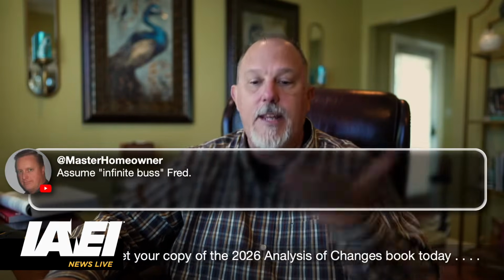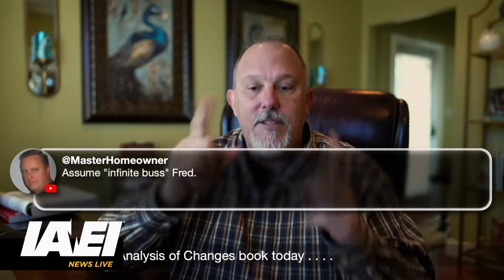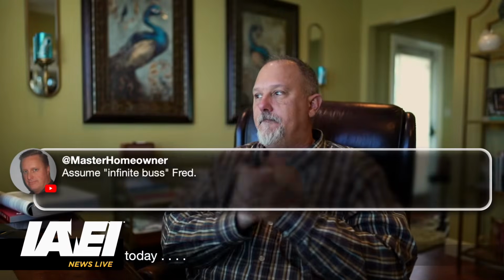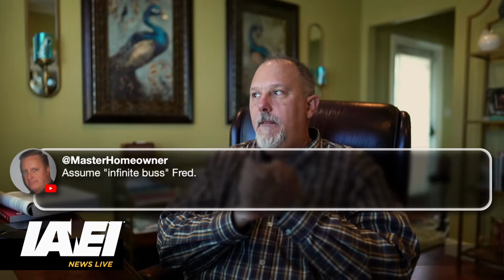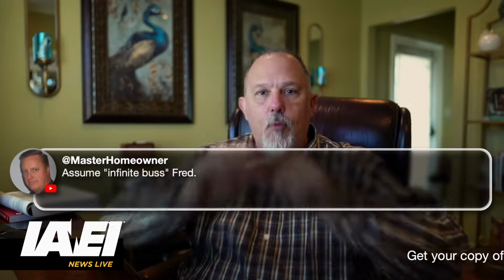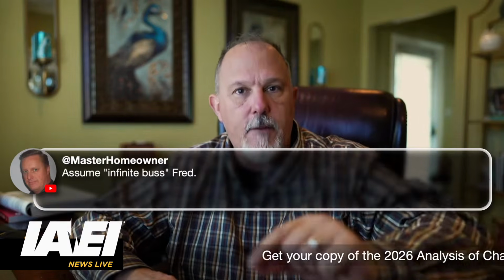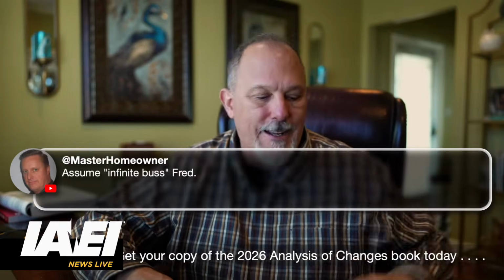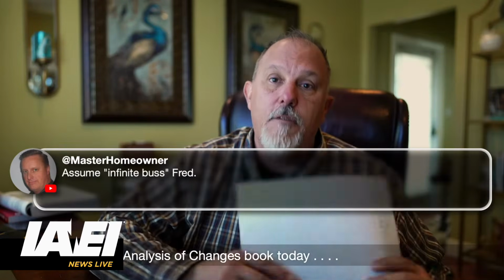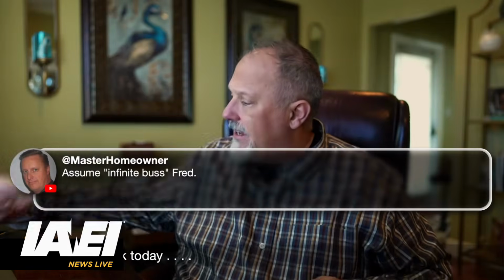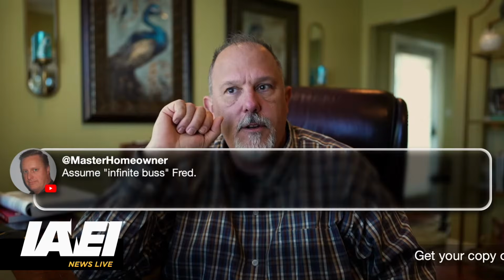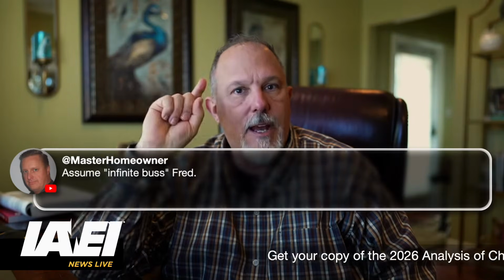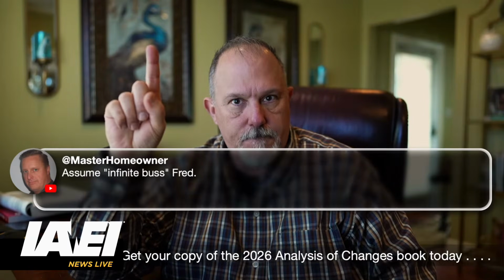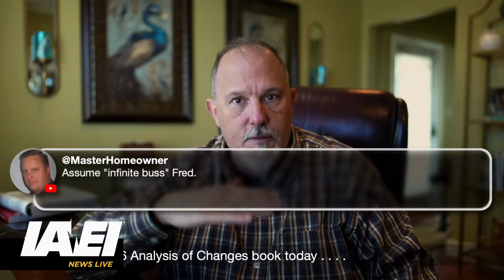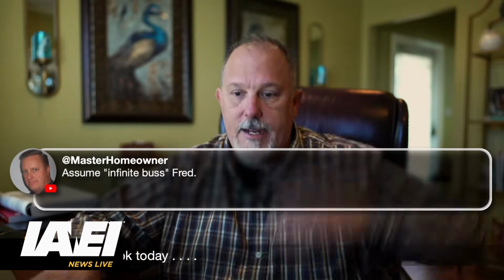All right, Freddie B. Assume infinite bus, Fred. Yeah, you assume infinite bus, but here's the thing, master homeowner. That works for interrupting ratings and short circuit current ratings. It doesn't necessarily work for incident energy, because lower fault currents can drive and will drive higher incident energy. So keep that in mind. Lower fault currents, longer clearing times.